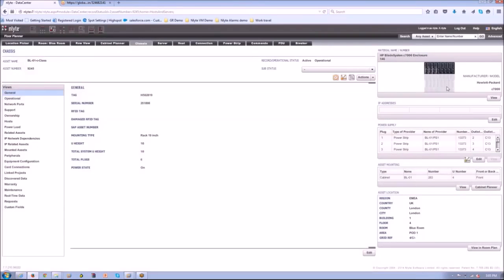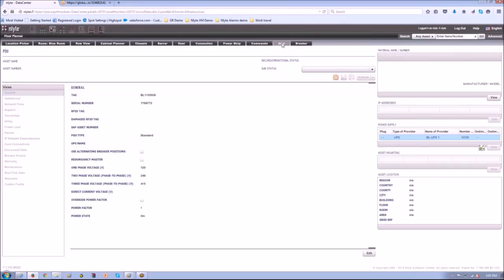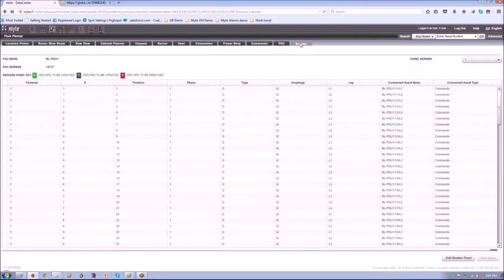So first of all, we start with a chassis. We choose an outlet from the chassis. We can go from there. We can trace the outlet to a particular power strip within the rack. From here, we can see the outlet on the back of the server and its power strip, or how it relates to the power strip itself. From there, we can go through. We can see how it relates to the commando or connection, whether it be ceiling or underfloor. And we can traverse this all the way up through the PDU, to a PDU, should I say, or a UPS, wherever it's in your power chain. And then finally to the breaker or the circuit panel inside a particular PDU or device. From here, we'll see the circuit we're connected to.